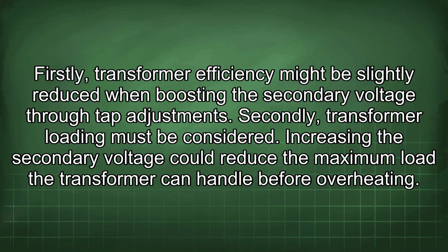Firstly, transformer efficiency might be slightly reduced when boosting the secondary voltage through tap adjustments. Secondly, transformer loading must be considered. Increasing the secondary voltage could reduce the maximum load the transformer can handle before overheating.